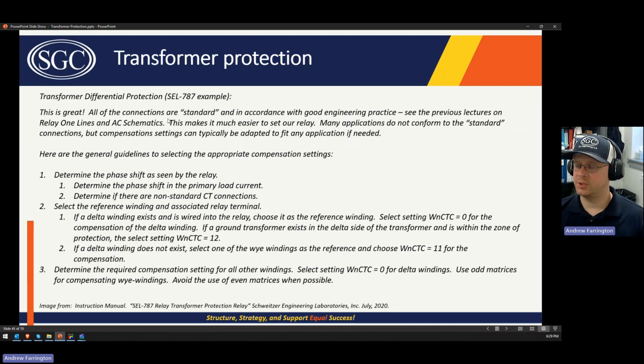So this is great. All of the connections are standard and in accordance with good engineering practice. See the previous lectures on relay one lines and AC schematics. This makes it much easier to set our relay. Many applications do not conform to the standard connections, but compensation settings can typically be adapted to fit any application if needed. Here are the general guidelines to selecting the appropriate compensation settings. We need to determine the phase shift as seen by the relay, which is determined by the phase shift in the primary load current. And if there are non-standard CT connections, then we need to select the reference winding and the associated relay terminal.